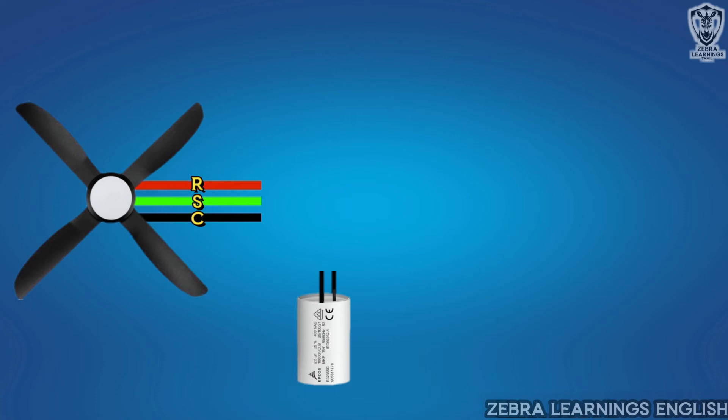The capacitor should be connected in series with the starting coil. That is, in the two terminals of the capacitor, one terminal should be connected to the common terminal, and the other terminal should be connected to the starting terminal.